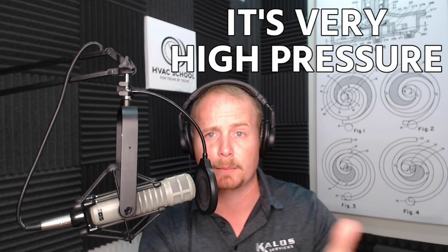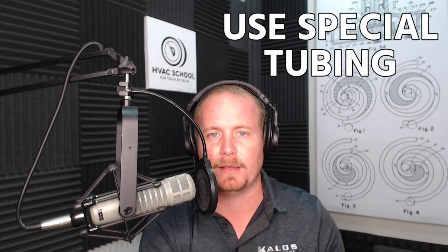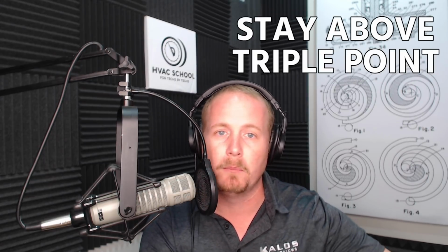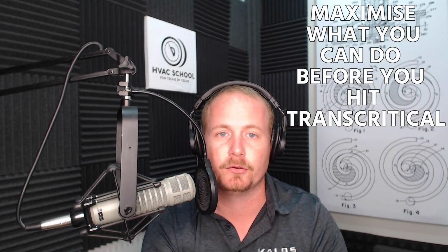One, because it's very high pressure. So when we're on the very high pressure side, we have to use special tubing, either stainless steel or copper, that's specifically designed for those really high pressures. It actually has some steel in it. And then we have to think of unique ways of designing the system in order to stay above that triple point on the lower level and to try to maximize what we can do before we hit transcritical. And so in this particular case, he's going to talk through the different controls and everything that goes into this transcritical booster system.